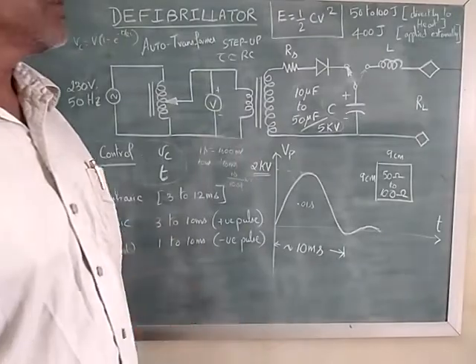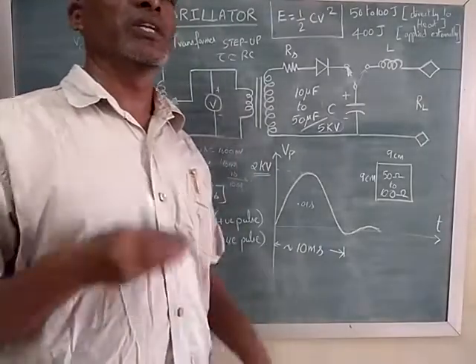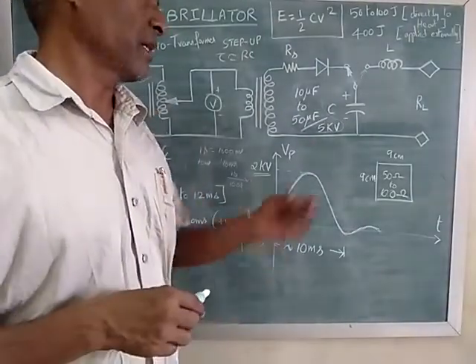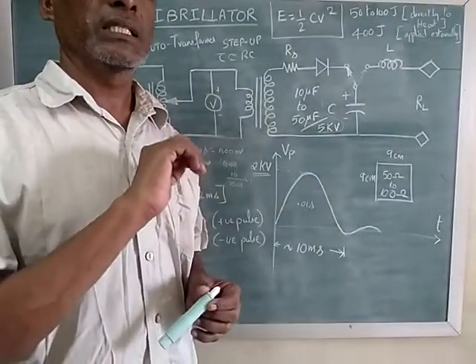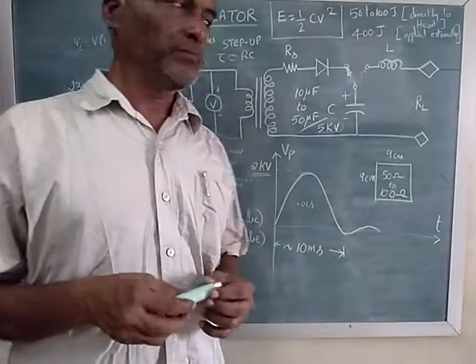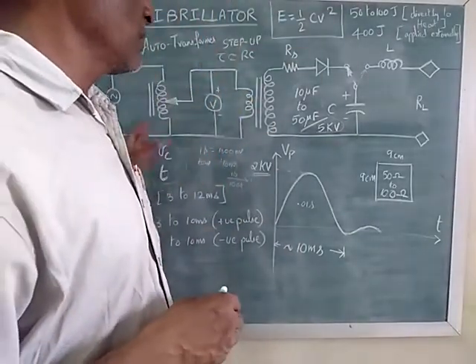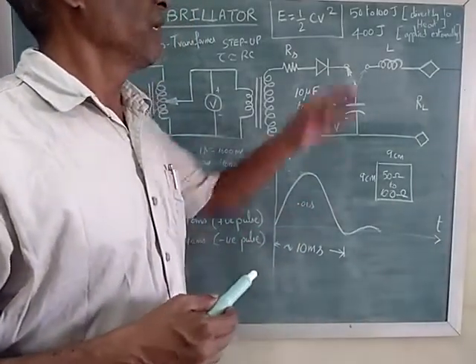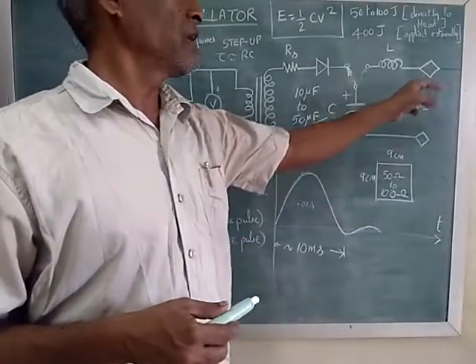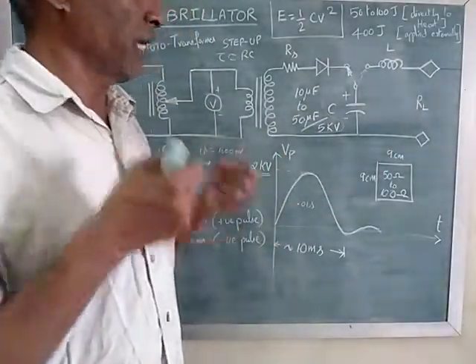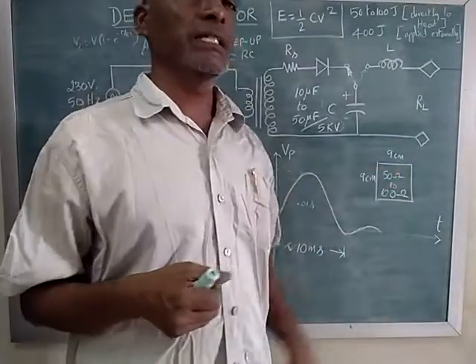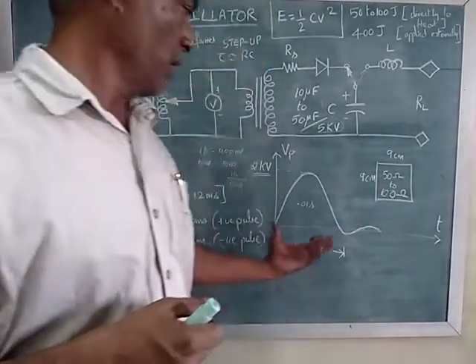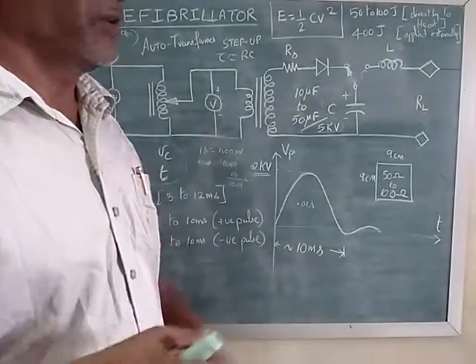So by this explanation, you know how the internal circuitry of a defibrillator works. The key component involved here is the capacitance, because you are making the capacitance charge and capacitance discharge. Also you come to know what's the voltage required, time required, energy required for different cases. What is the area of the plates that is placed, that the electrode size, 9 centimeter into 9 centimeter, approximately 81 centimeter square, and the resistance of the plates. The typical shock waveform given to the patient.